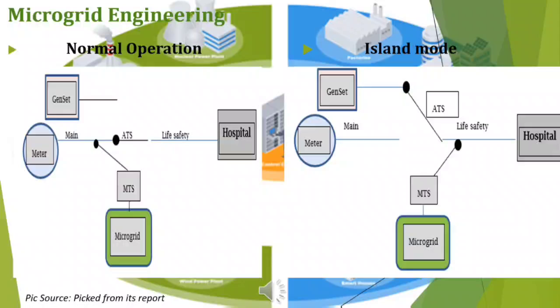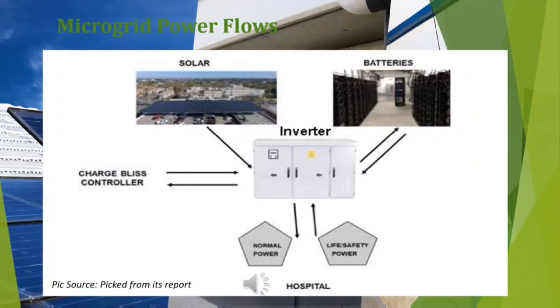During normal operation, the diesel generator, indicated as genset, remains idle and disconnected while power is supplied from the utility across the main meter and the microgrid. Here, if the AC port real power set point, normally provided by supervisory control, is less than PV power, then the excess goes to the battery until the high state of charge limit is reached. If the AC power set point is greater than the PV power, then the difference comes from the battery until the low state of charge limit is reached. Next, the mode of operation: island mode.